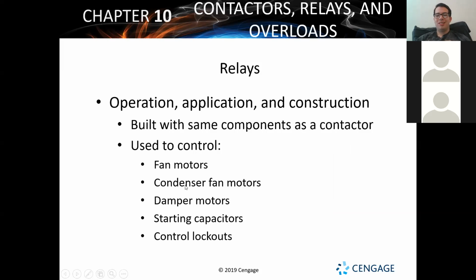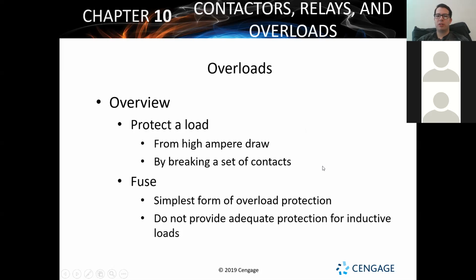Again, fan motors, some condenser fan motors, damper motors, definitely - you've got it where they use relays sometimes for the starting capacitor, because that's only going to be operating when the motor first starts up. So the relay kicks on, turns on the start capacitor, we're up to speed, turns off the start capacitor, the relay disconnects, and it makes life really easy. So a relay is the same thing as a contactor, just smaller - that's the big difference.